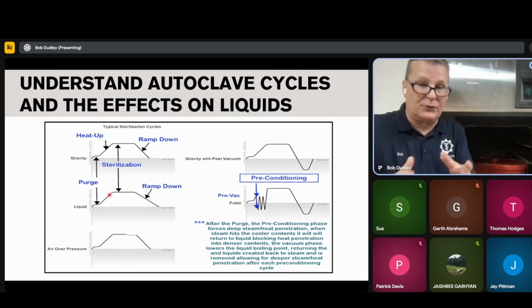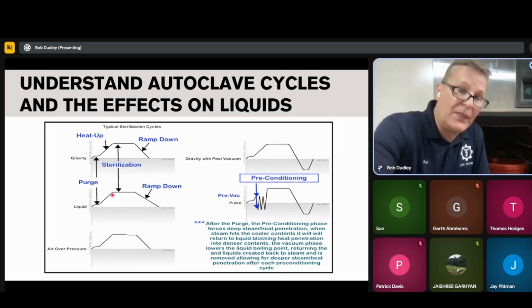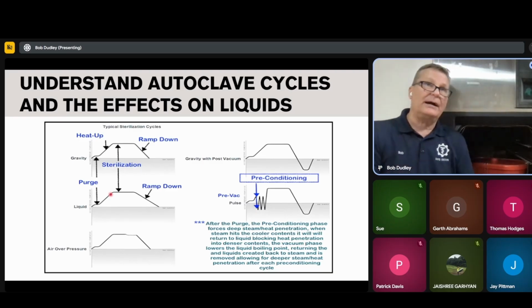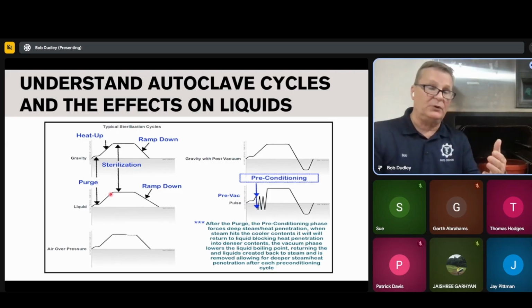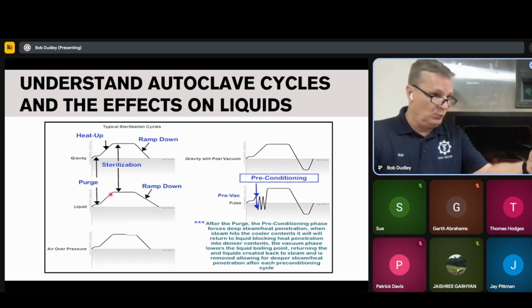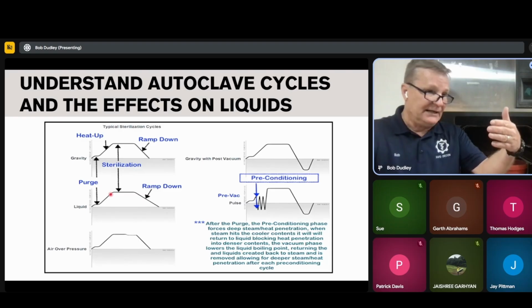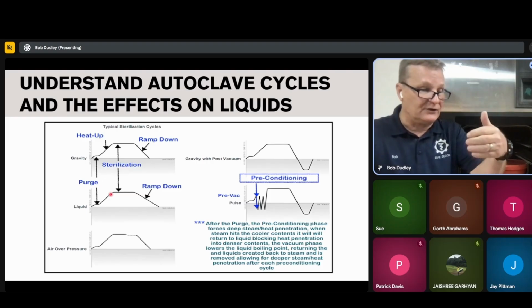So it has to make sure that everything's in place. And then it's going to do a last drop rate check before it gets to sterilization. And what I mean by drop rate is the autoclave is going to go, we have an acceptable level to where when we get to 13 psi or 118 Celsius, what's going to end up happening is how much drop in temperature is going to happen before we kick over to sterilization.